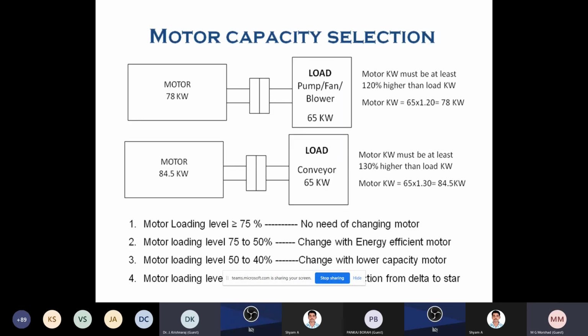So the lower size motor, how are we going to make it effective? See, if the loading level is greater than 75% of the motor, no need of changing the motor. Because the efficiency of the energy efficient motor is maintained up to 50%. So if the motor loading is 75 to 50%, use an energy efficient motor. If the motor loading is less than that, you change the motor capacity to a lower one. And if motor loading is less than 40%, you can change the delta motor to the star motor. So this is the recommendation I had implemented in my plant and run it successfully, so that it was used very properly without much investment. Because investment also is a very, very important factor.